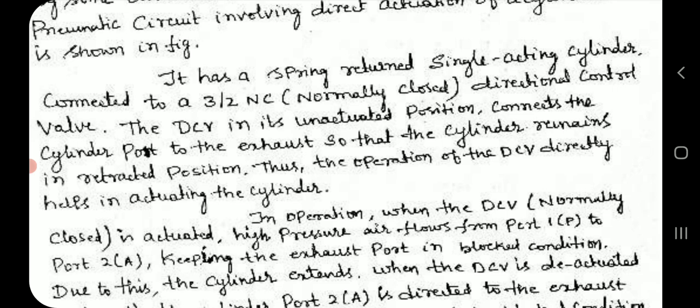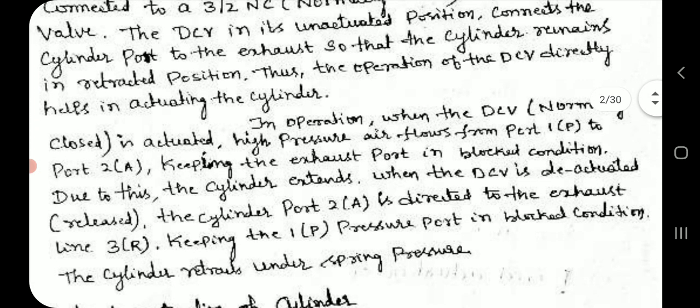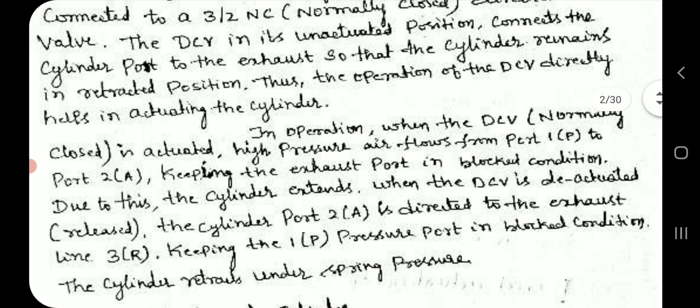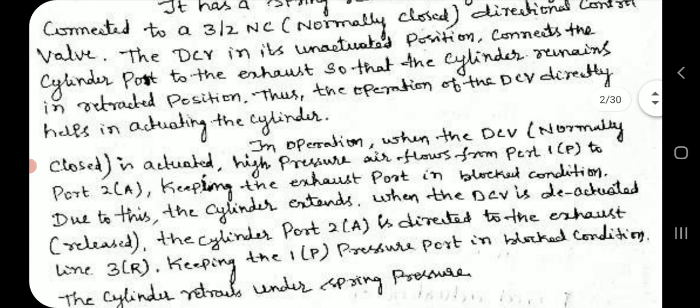In operation, when the normally closed directional control valve is actuated, high-pressure air flows from port P to port A, keeping the exhaust port in a blocked condition, causing the cylinder to extend. When the directional control valve is released, the cylinder port A is directed to the exhaust port R, keeping the pressure port P in blocked condition, and the cylinder retracts under spring pressure.